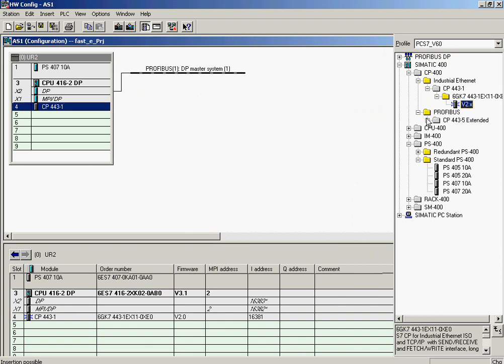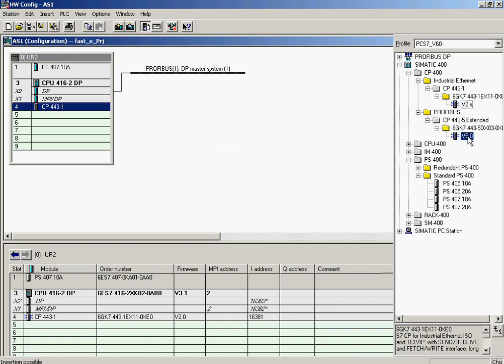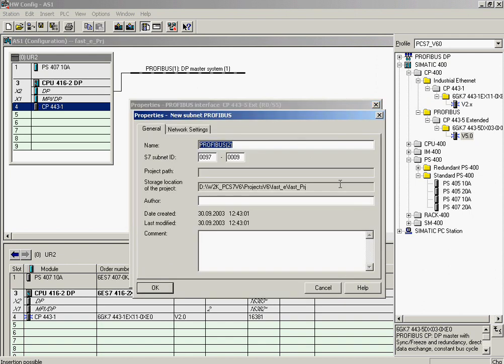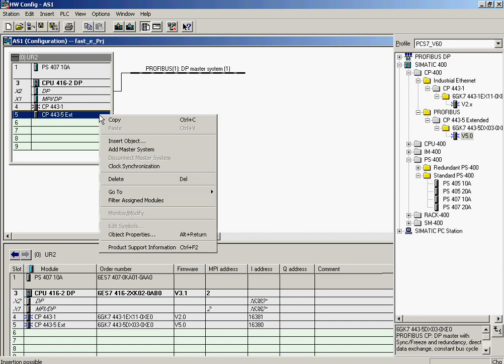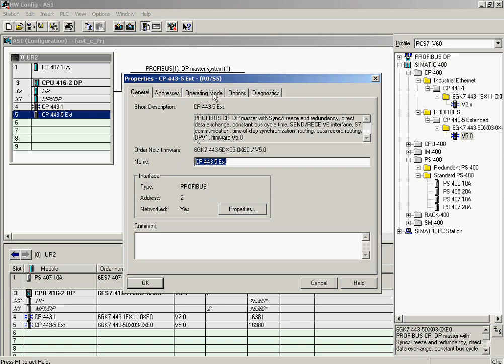The CP443-5 Extended is configured for access to the PROFIBUS. Some adjustments are made in the properties dialog. The first step is to create a new PROFIBUS string, which will have the name DP1. The last step is to open the properties dialog with the right mouse button and set the CP operating mode to DP master.